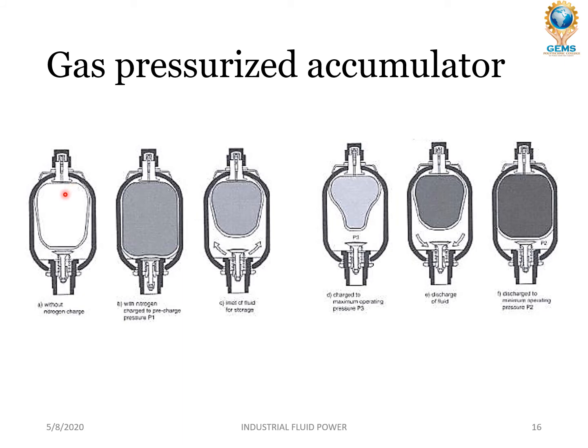Initially the accumulator is empty and the bladder is fully expanded with gas — here it is filled with a nitrogen charge. When pressurized fluid enters, it compresses the bladder. The bladder compresses to the maximum extent it can. When pressure is needed and low pressure is created on the system side, the pressurized fluid comes out, and the bladder expands from its compressed state back to its decompressed stage. The pressure fluid then goes and compresses the bladder again on the next charging cycle.